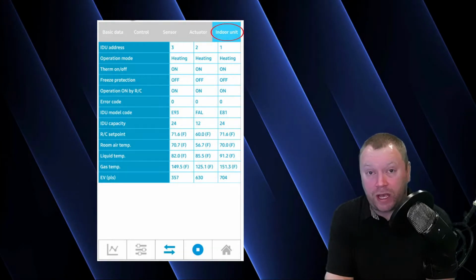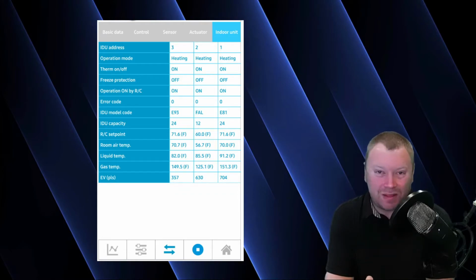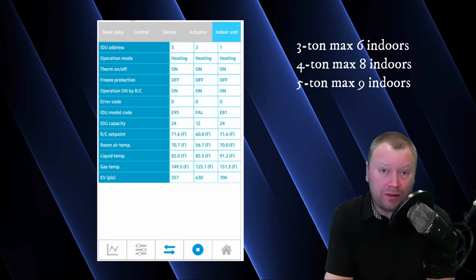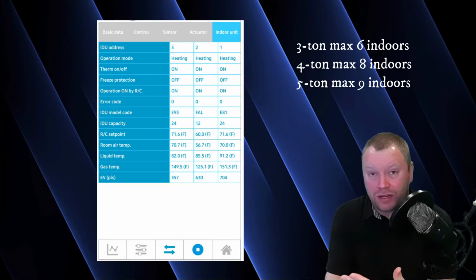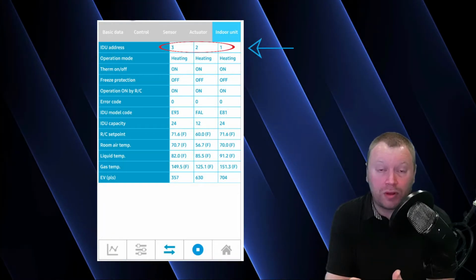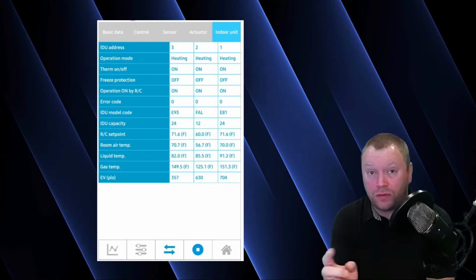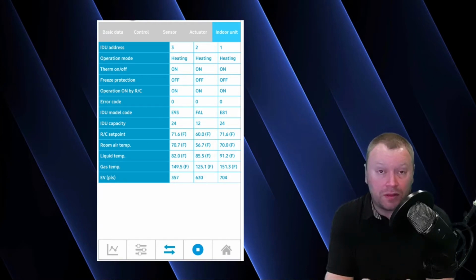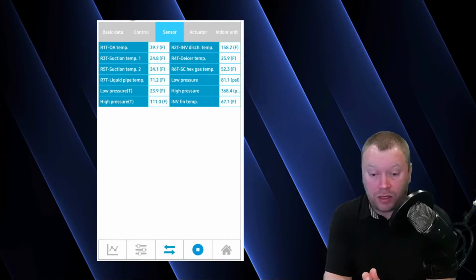And then your indoor tab is going to have all of the indoor unit information for all of the indoor units that you have on your system. If you have one indoor unit on your VRV system, you're going to have one indoor unit shown here, and up to 8 indoor units can be shown here because that is the maximum number of indoor units you can install, unless you have a 5-ton, in which case you can have up to 9. And in that case, you can see here, I only have 3 on my house, but if you did have more than 3, you would just simply scroll over through all of your indoor units. So very easy to navigate. And then from there, you would just click on the different tabs at the top to navigate from tab to tab. Okay, so let's take a look at our first loop.